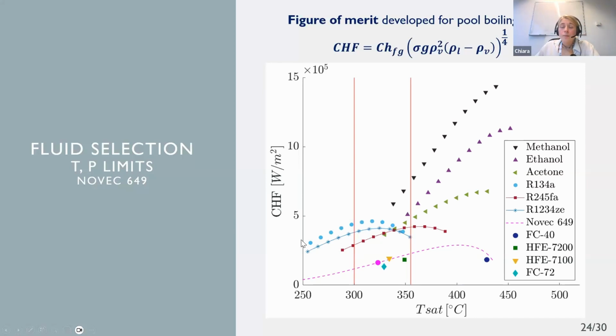Of course, there are huge differences, but in this plot we don't see the operating pressure. For example, for fluids such as refrigerants R134A, 245, and 1234ZE, these three curves show critical heat flux much higher than NOVEC, that's the pink curve, but they have to run at much higher pressures.